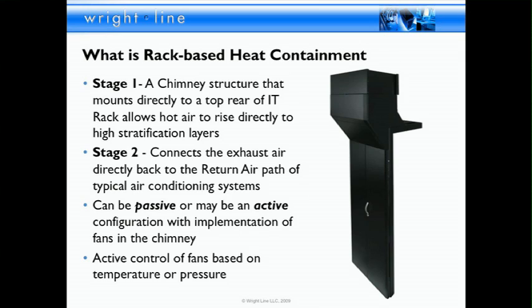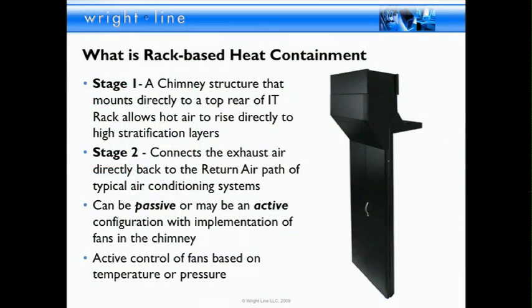Why rack-based heat containment? Stage one is a chimney that directly connects to the rack to exhaust that heat and throw it up into that stratification layer, without it just being exhausted straight out the back of the rack and relying on normal heat rise to get that heat up into the stratification layer. Stage one, we see it as a way to facilitate that stratification return concept. Stage two is that same chimney connected to a return plenum. And when it's connected to the return plenum, and actually in stage one as well, you can make that active or passive. Passive systems exist, active systems exist. We do them both regularly. And when it's active, you can look at controlling it via temperature or via pressure, whatever is really your driver.